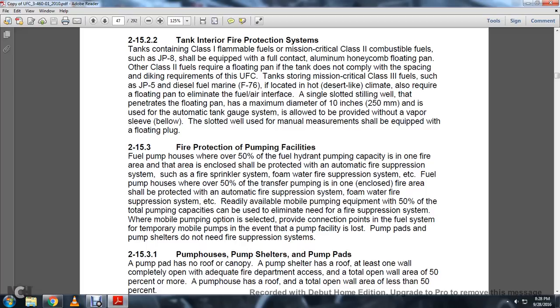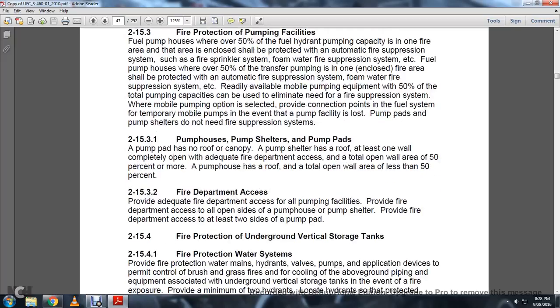The pump pads and the pump shelters do not need fire suppression systems. 2-15.3.1 Pump houses, pump shelters, and pump pads. A pump pad has no roof or canopy. A pump shelter has a roof with at least one wall completely open with adequate fire department access, and a total open air wall area of 50% or more. A pump house has a roof with a total open air wall area of less than 50%.